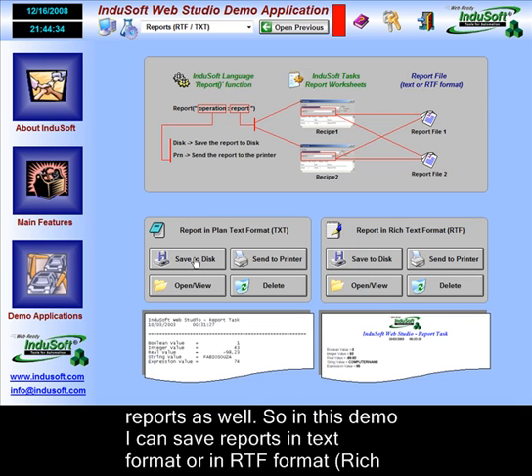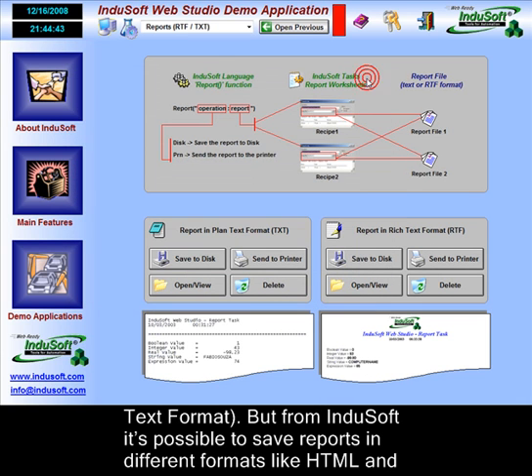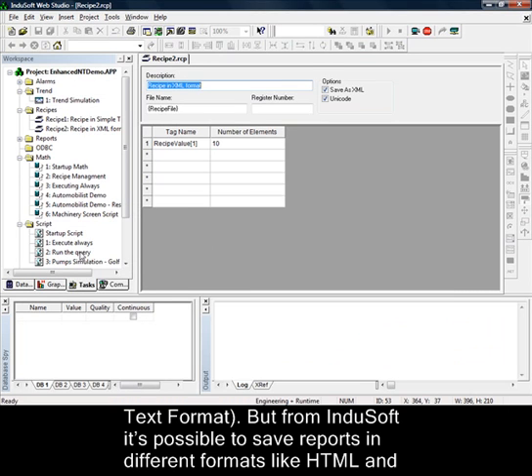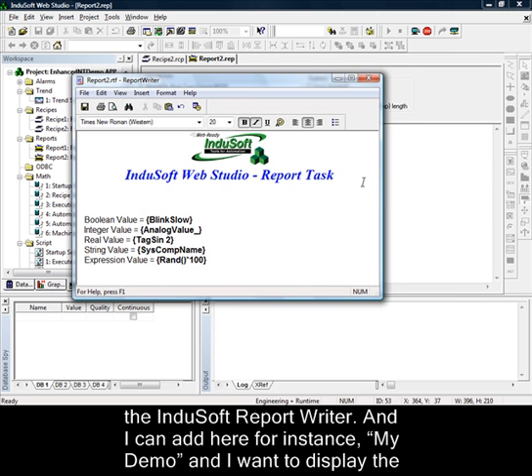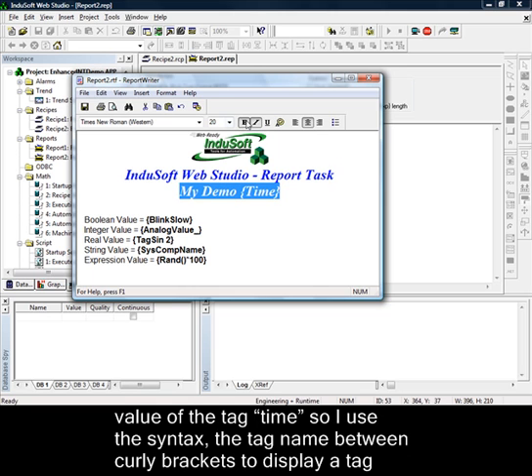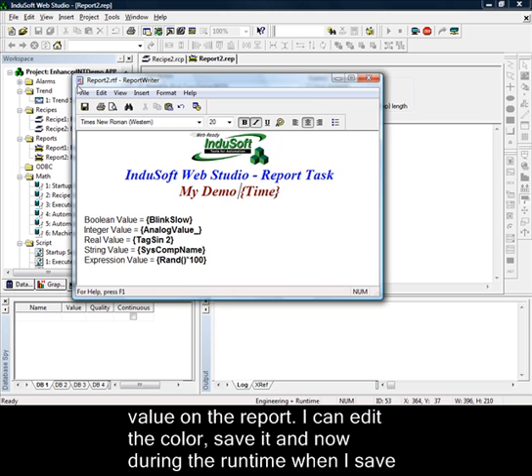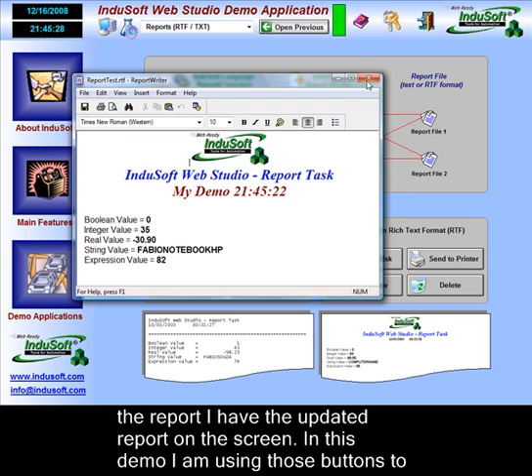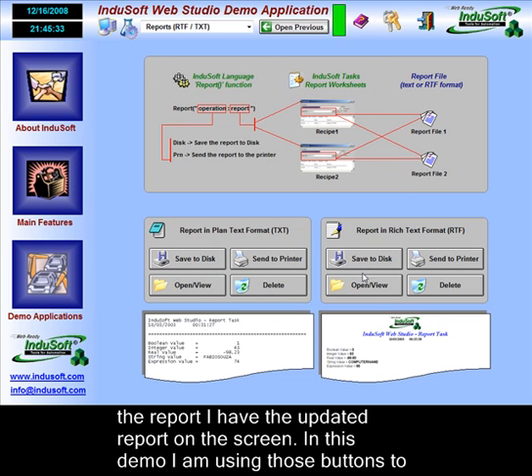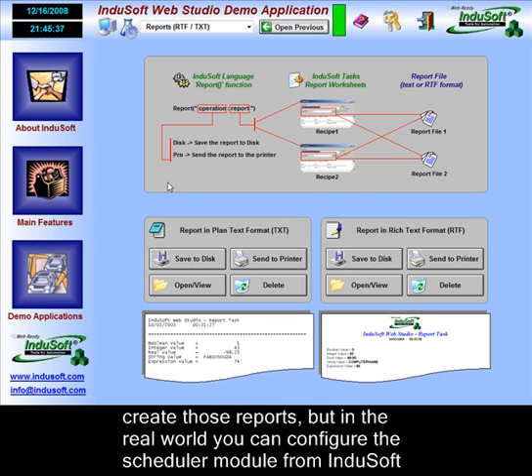Indusoft provides an embedded tool to generate reports as well. In this demo, I can save reports in text format or in RTF format — rich text format — but it is also possible to save reports in HTML and PDF formats. If you want to change the report, it's as simple as editing it in the Indusoft report writer. I can add content here — for instance, to display the value of the tag time, I use the syntax with the tag name between curly brackets. I can also edit the color, save it, and during the runtime when I save the report, I have the updated report on the screen.